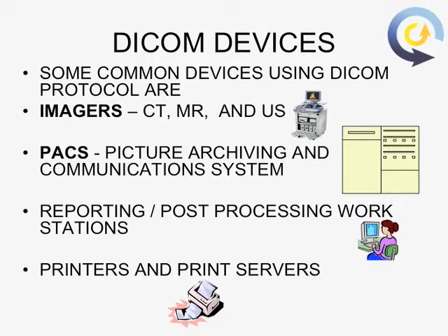DICOM devices. Some common devices using the DICOM protocol are imaging devices such as CT, MR, and ultrasound, picture archiving and communication systems — commonly referred to as PACs — reporting post-processing workstations, printers, and print servers.